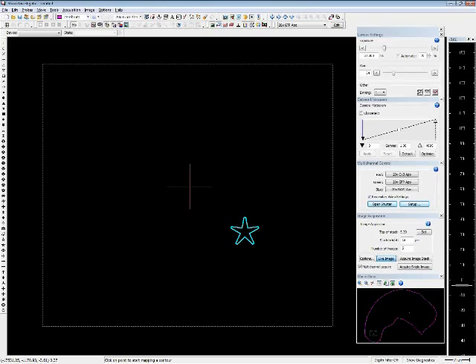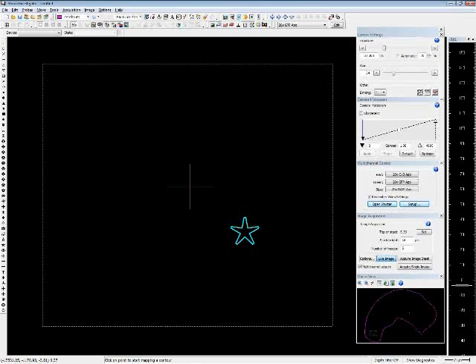Next, we need to learn how to focus the grid for each objective and filter combination. As you will see later, this is very important in the process of acquiring multi-channel images. You will want to do these calibrations over a region or with a slide that is not precious, to avoid bleaching your most important tissue.